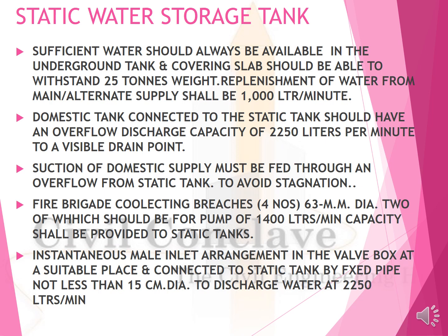A domestic tank connected to the static tank should have an overflow discharge capacity of 2250 liters per minute. The domestic supply must be fed through an overflow from the static tank to avoid stagnation. Fire brigade collecting breechings: 4 numbers of 63 mm diameter, 2 of which are for a pump of 1400 liters per minute capacity, shall be provided at the static tank. An instantaneous male inlet arrangement to the valve box at a suitable place is to be connected, not less than 15 centimeters in diameter. The discharge of the water should be 2250 liters per minute.